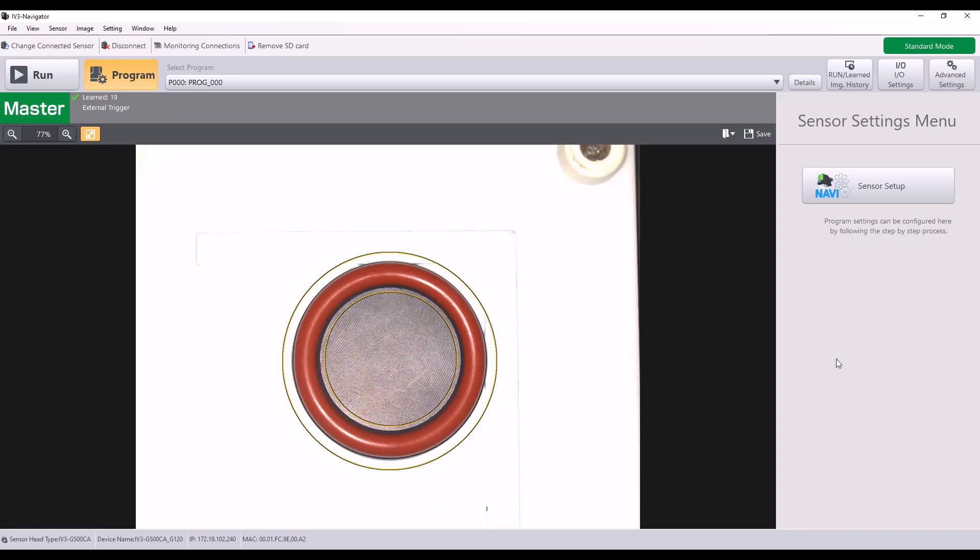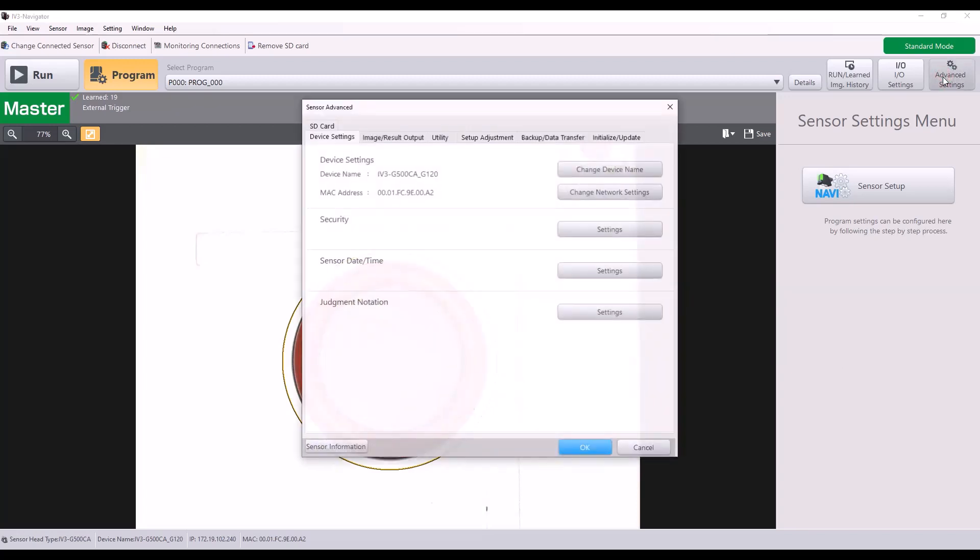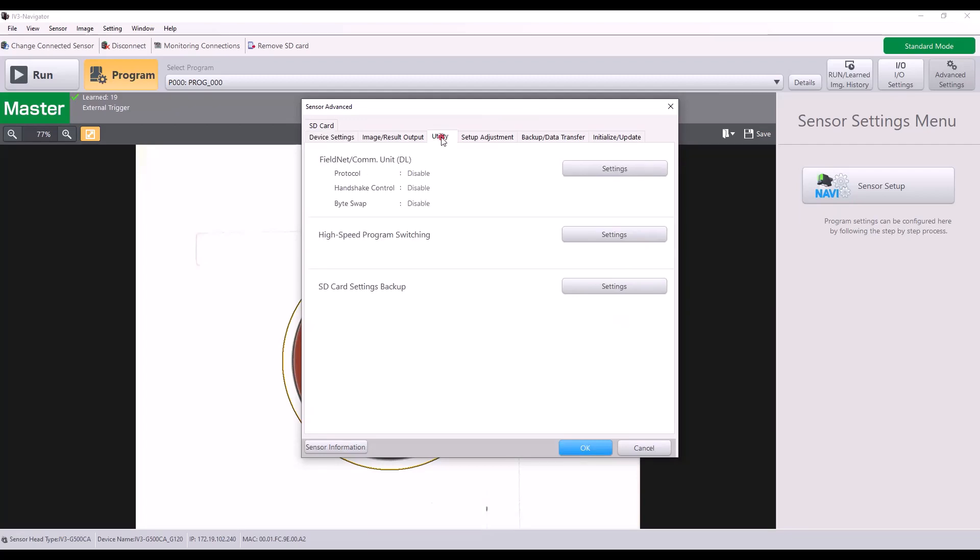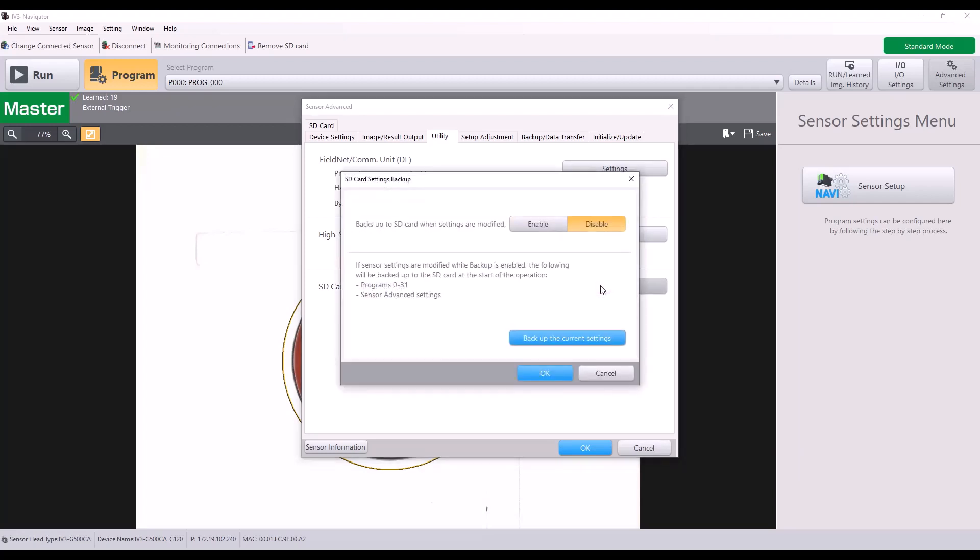So the last function of the SD card is automatically backing up the sensor settings to the SD card. To do that, you go to the advanced settings and the utility tab. And there's a setting called SD card settings backup. If I go ahead and press OK, I can enable this setting. And now anytime settings are modified in my program, it will automatically back up to the SD card.